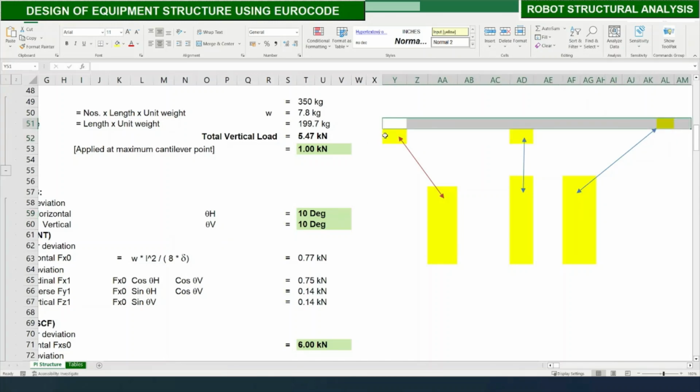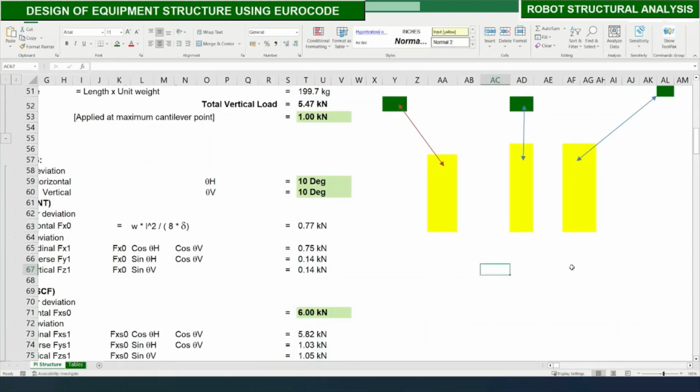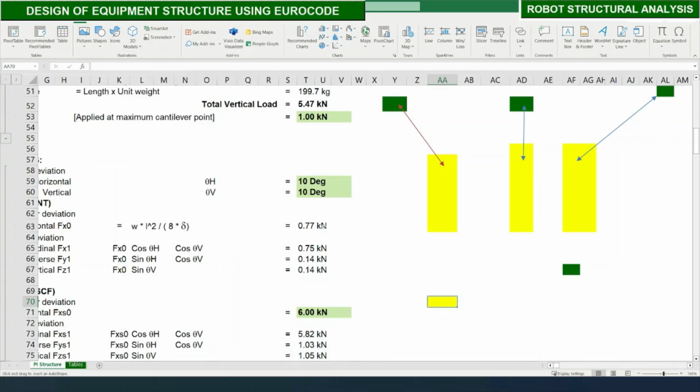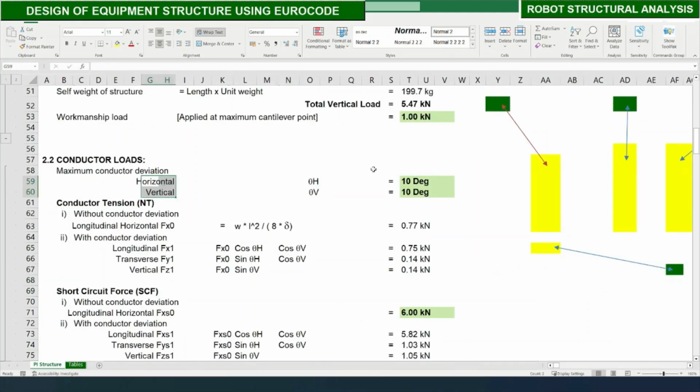Assume this is a transformer, this yellow color is the transformer bushing. If the transformer bushing is far away or not aligned on the same axis of the PI, then the conductor will have some deviation in horizontal. Similarly in vertical also, suppose the transformer bushing is at this level and the PI is at a lower level, then there will be some push. Generally this won't happen; this PI will be at a higher level. So here the vertical inclination will be there. That is what we are considering here.